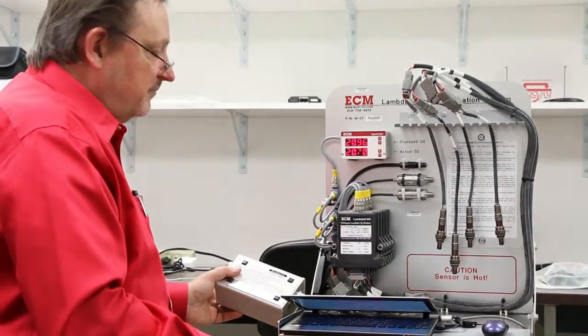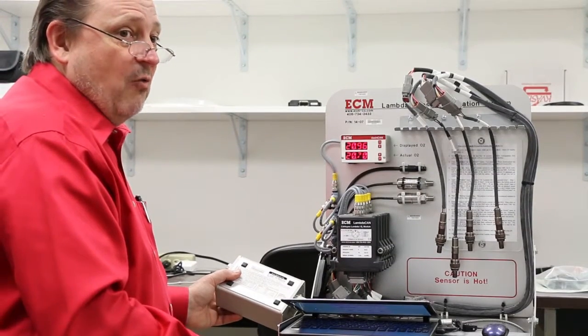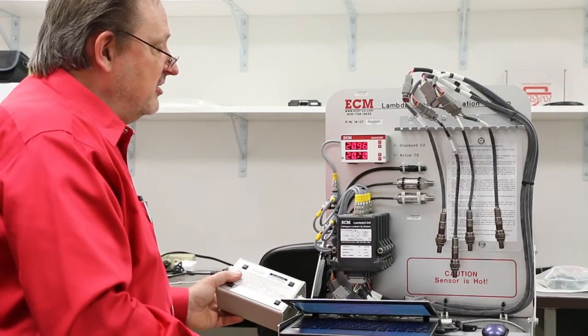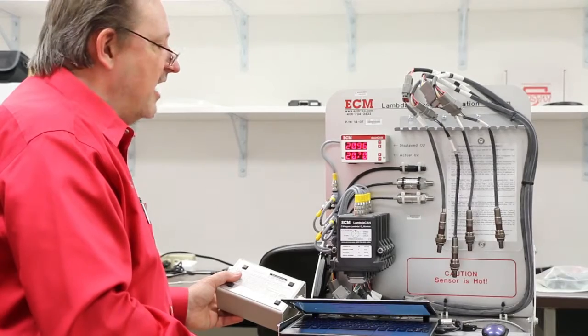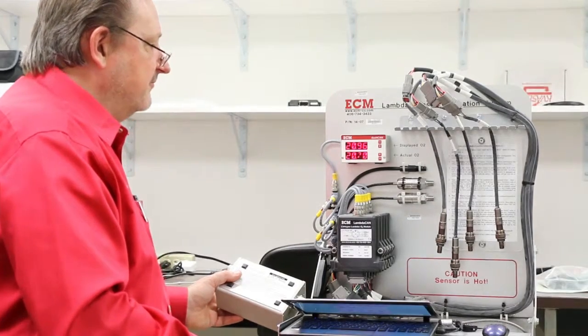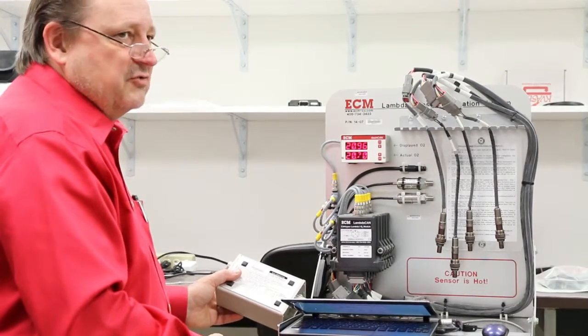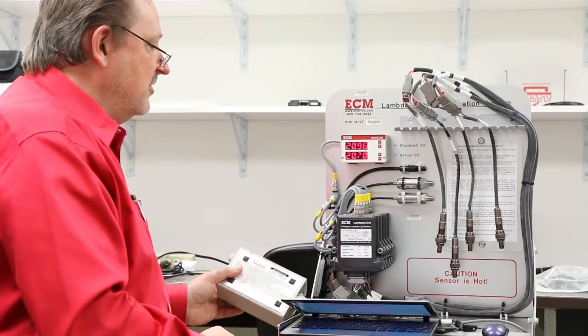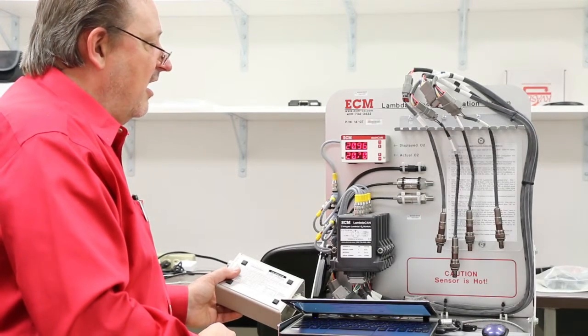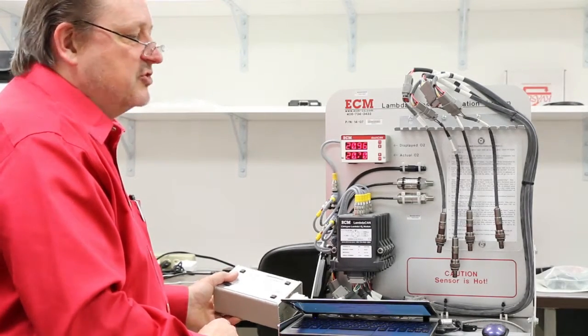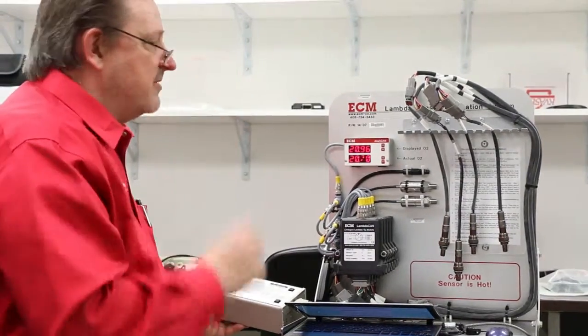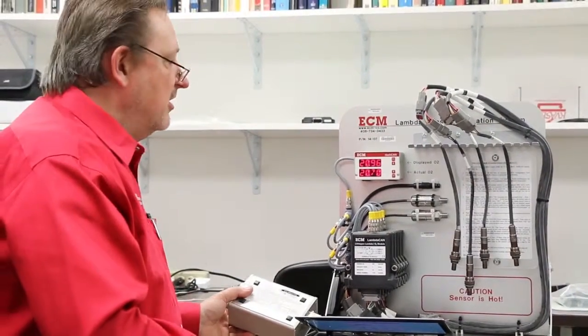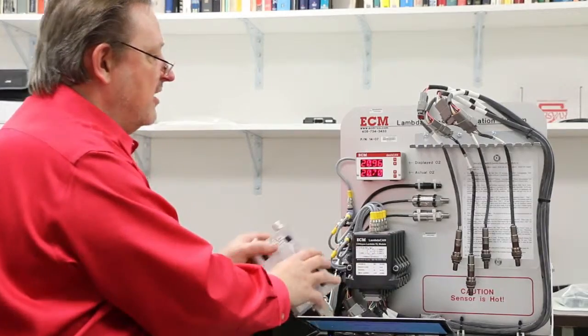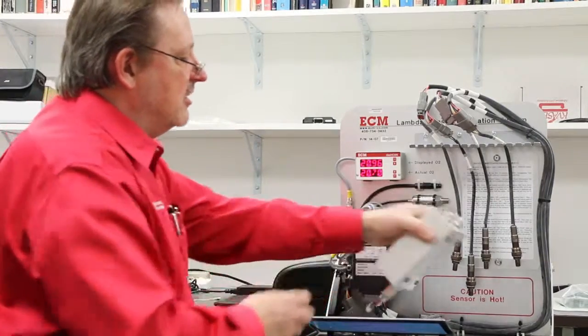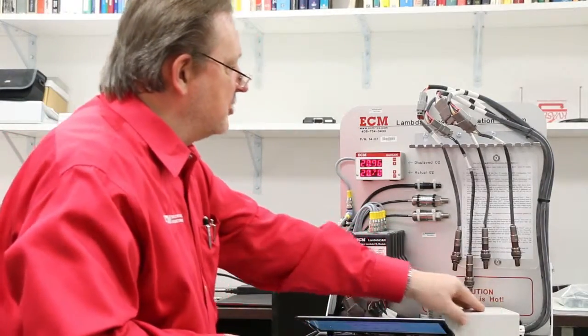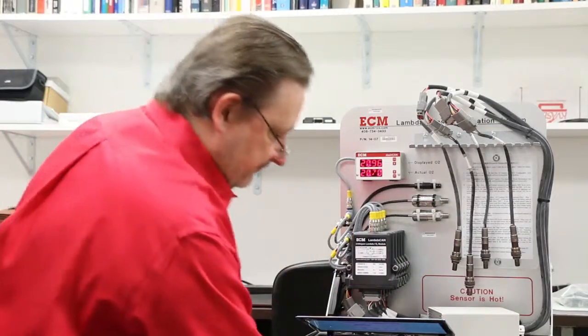This you only need to do once a month, and frankly, in units that are used indoors and dynamometers, you don't see these things drift a lot, but we recommend you do this once a month. In vehicle applications or where there's a power supply blowing up or something weird happened, the cable got burnt, and you're just wondering the health of this unit, this is very handy unit to use. So in this case, you could check all 4 of them.